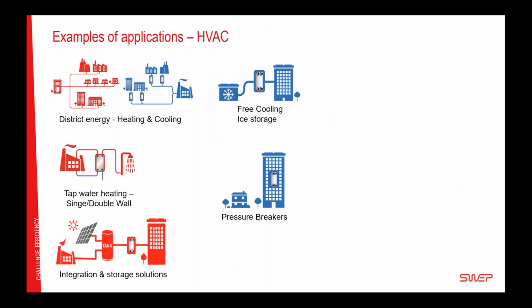Where can you find brazed plate heat exchangers? Let's start with the HVAC market. We can find them in district energy, distributed heating or cooling. Typically you have a central making heat or a central making cold, and then you go by different steps out to the end user. The closer to the end user you get, the smaller the heat exchanger, and the closer to the central you get, the larger the heat exchanger. The brazed plate is very common close to the user, but with increasing size, as you've seen that we have, the brazed plate is getting closer and closer also to the central, both for heating and cooling, because the brazed plate technology is efficient, compact, and cost effective.